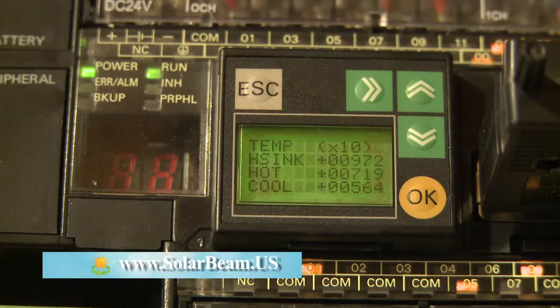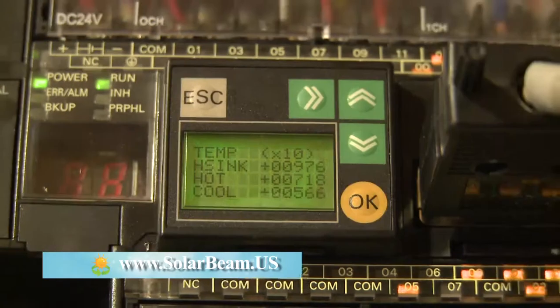The next one is called the hot. That is the hot water coming out of that absorber. It says here 71.9 degrees Celsius. And this has been on for about 2 or 3 hours. By another 2 or 3 hours from now, that'll be up to about 80 or 90 degrees Celsius. The cool is the water that is coming in from the home, and that is at 58 or 56.4. You can see the delta T in this case is about from 56 to 71 is around 14 degrees.